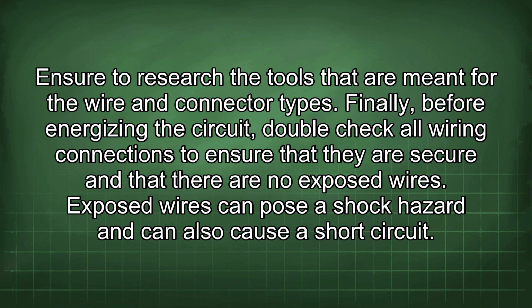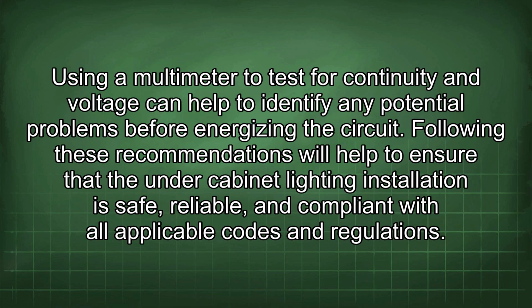Finally, before energizing the circuit, double-check all wiring connections to ensure that they are secure and that there are no exposed wires. Exposed wires can pose a shock hazard and can also cause a short circuit. Using a multimeter to test for continuity and voltage can help to identify any potential problems before energizing the circuit. Following these recommendations will help to ensure that the under-cabinet lighting installation is safe, reliable, and compliant with all applicable codes and regulations.